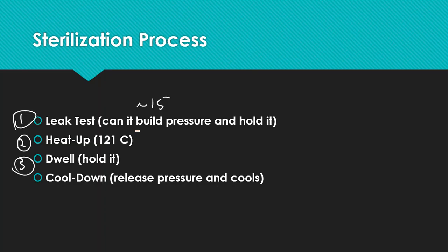And number four, there's always going to be a cool down process, and that cool down process will slowly vent, and it will lower the pressure and lower the temperature down to a point where, in a laboratory setting, you can open the door and take out the tools that have now been sterilized. In a manufacturing type of setting, it's now safe to use, and we can put it back into the manufacturing line and get it back up and going again, making product. And making product means making paycheck.